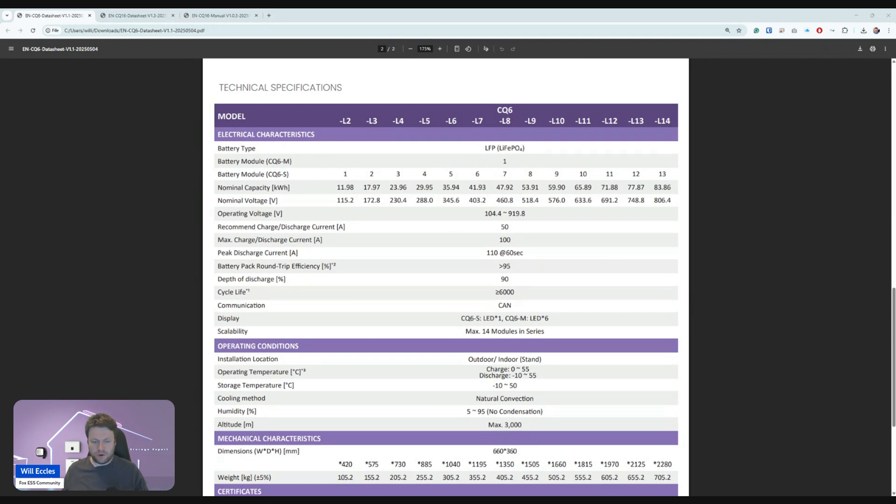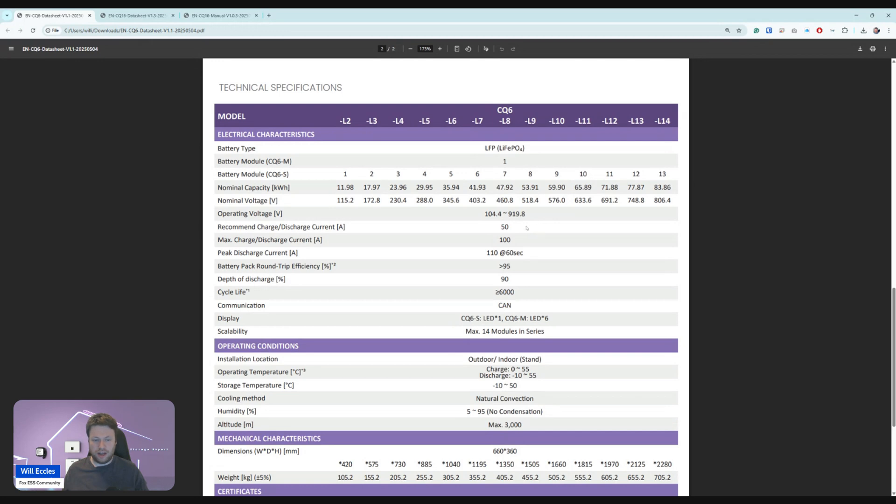The voltage range is another interesting thing to call out on the spec sheet. It goes right up to over 900 volts, which means that it's not going to be compatible with any of the single-phase systems currently because they are limited, I believe, to 500 volts, and especially if you're on one of the more earlier H series models where they're 400, 450 volts or 440 volts.